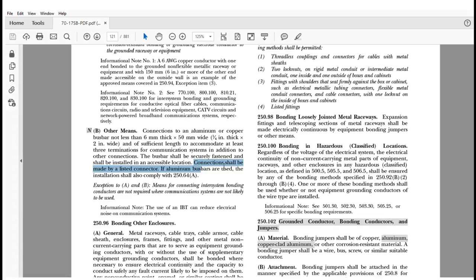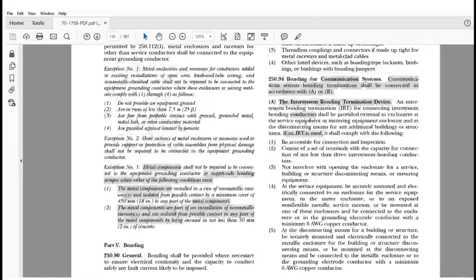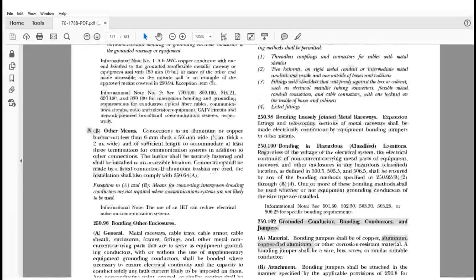You can't use this communication device to do that because it has a specific need, okay? But you can use this other means, and as long as the bus bar meets the size and there's a sufficient length, it may have at least 3 terminals for the communication aspect, and then any additional terminal space available to meet the other aspects. No, I can't put one on top of the other and connect it to the same lug as the communication, because then that means that you didn't provide the adequate length for the 3 terminals for the communication in addition to the other connections. So you need an additional length in order to be able to make those independent connections.